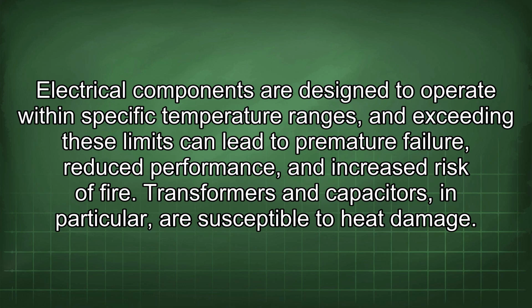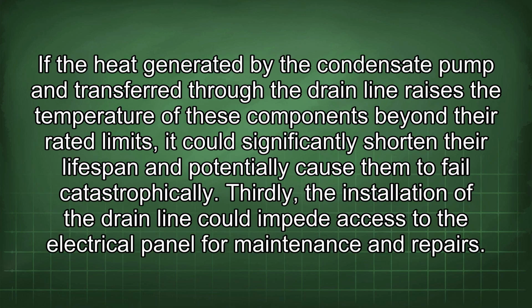Transformers and capacitors, in particular, are susceptible to heat damage. If the heat generated by the condensate pump and transferred through the drain line raises the temperature of these components beyond their rated limits, it could significantly shorten their lifespan and potentially cause them to fail catastrophically. Thirdly, the installation of the drain line could impede access to the electrical panel for maintenance and repairs.